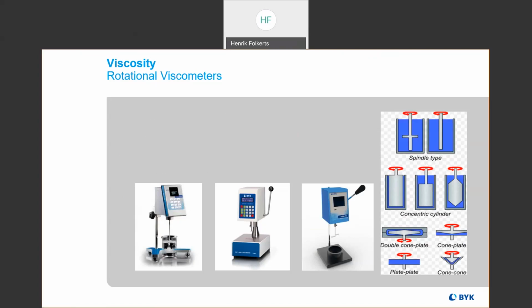And for somewhat more precise viscosity measurement, we also have rotational viscometers. The idea is you take a container full of your liquid and you stick a spindle down into the liquid, and the spindle spins through the liquid. From the resistance that the spindle experiences, that spindle is of course connected to the viscometer, which is causing it to spin, and also measuring the torque, the resistance on that spindle as it spins due to the viscosity of the liquid. So the more torque experienced by that spindle as you spin through, the more resistance it's feeling, the higher the viscosity of the liquid.